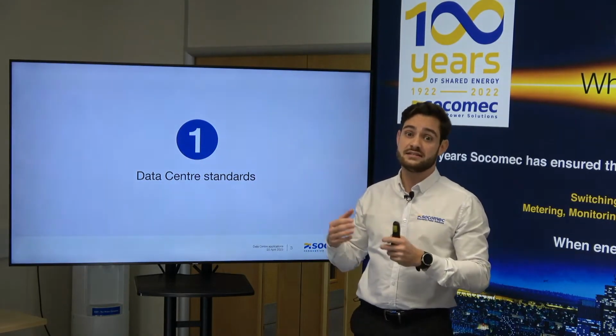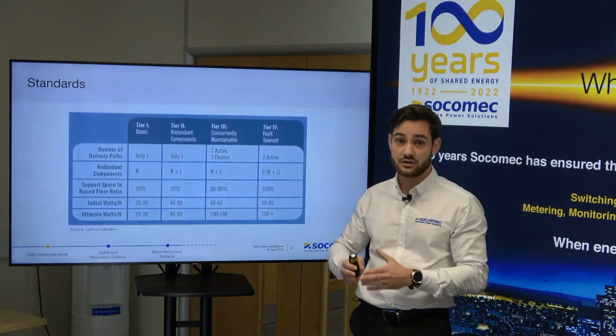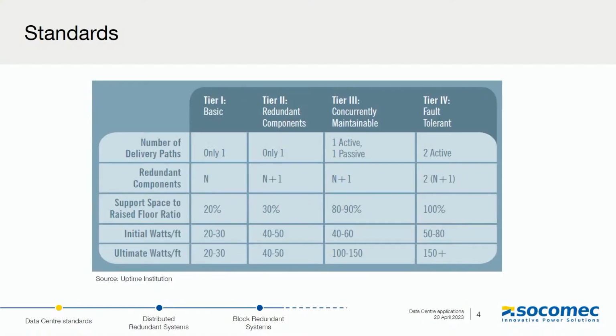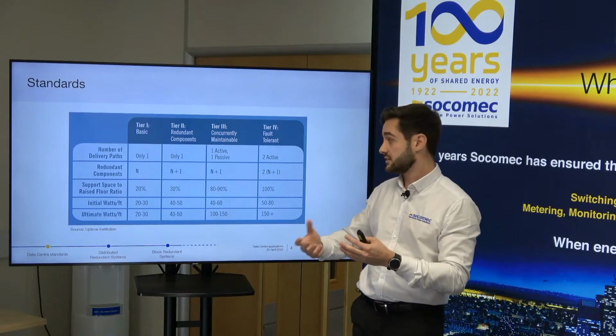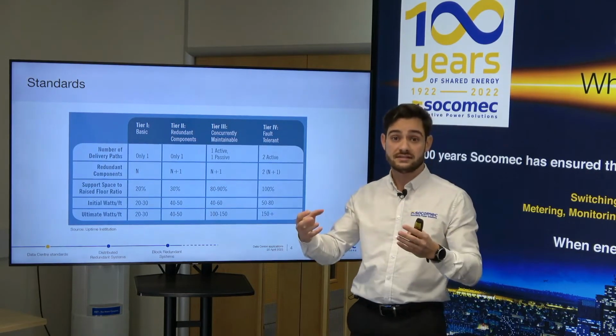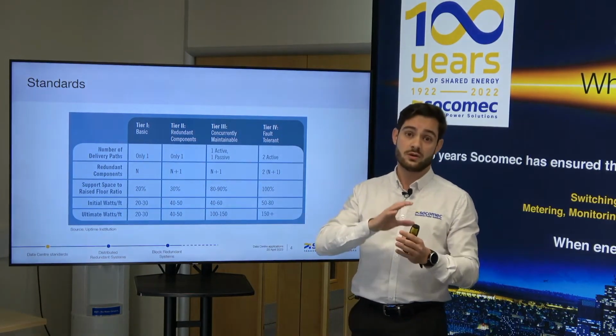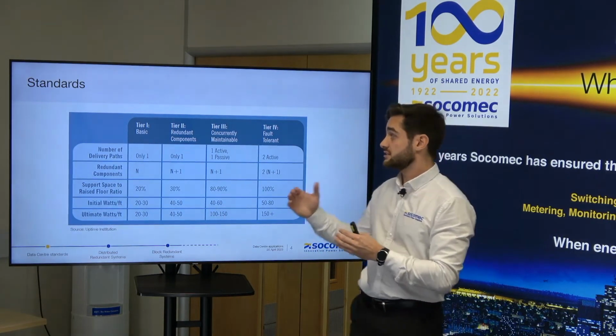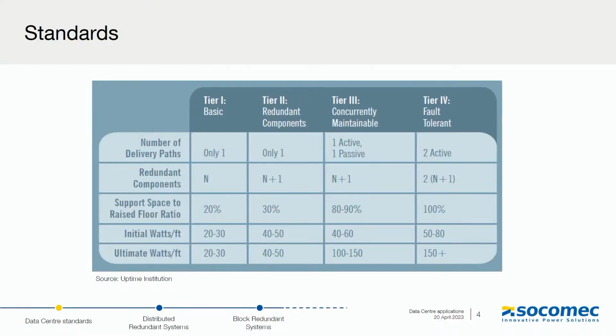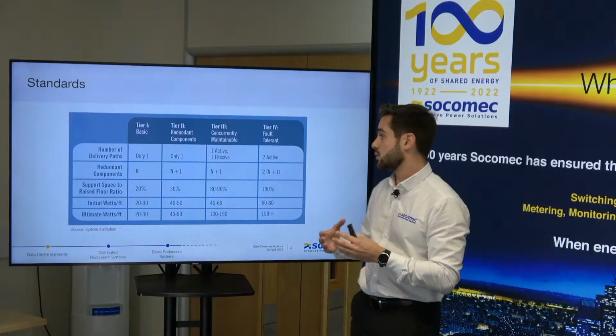It has created a tier classification from tier 1 to tier 4. As we can see here, tier 1 for a data center will really be the basic. What we mean by basic is you would get your IT servers, so your loads. Then you would get a UPS system, a cooling system, and a generator for power outage. Then we go to the next level, which is the tier 2 data center. On this one, we can have some redundancy on some components, for example on the UPS system and the cooling system. And then tier 3 and tier 4 is where we will be focusing on.